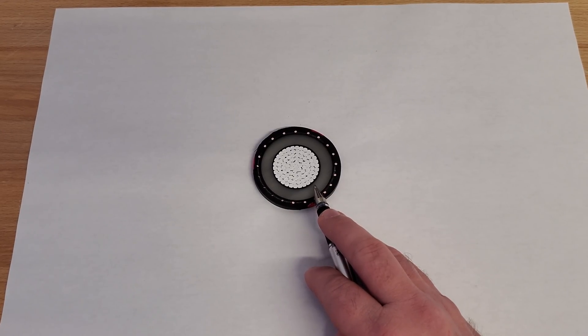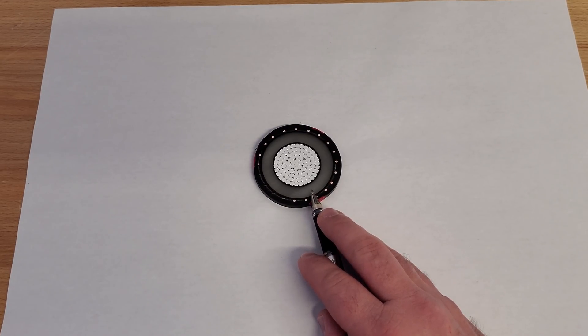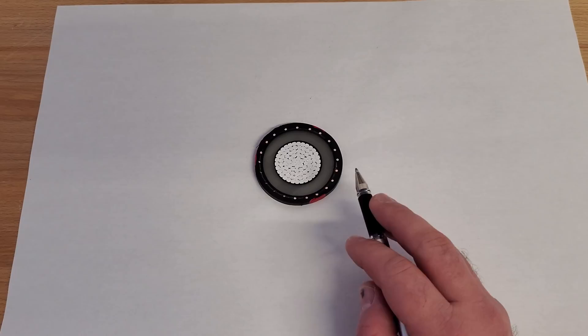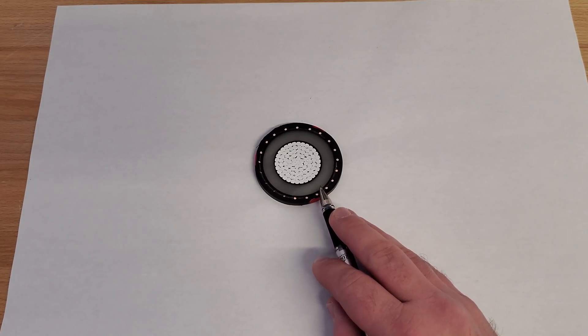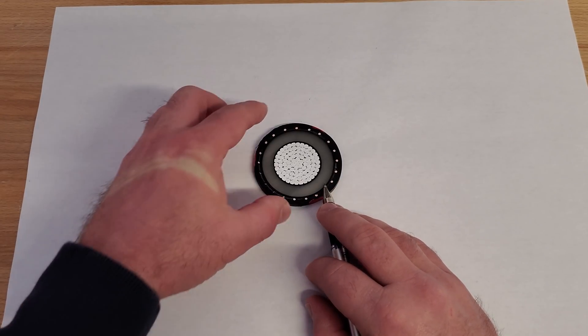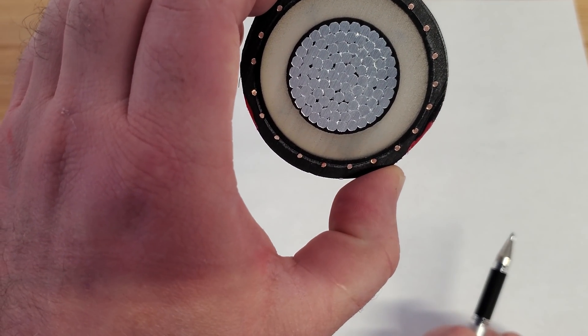And this is 345 mils, which is 345 thousandths thickness. There's a lot of IEEE tables and different tables that will tell you what the insulation thickness is supposed to be. You can actually buy a cable with a higher insulation rating than you need to. This is 100% insulation, which means that's what you need to operate this cable safely. You can also purchase 133% and 166%. A lot of people like that extra fluff in there. If you've got transient voltages and things like that, you want to make sure don't break your insulation down over time. This here is 100% insulation. And it's called XLPE and it's actually fairly transparent. I don't know if you can see that too well. It depends on the thickness that you cut this.